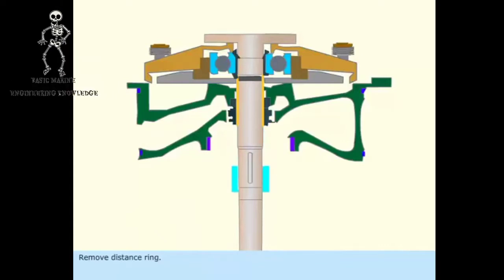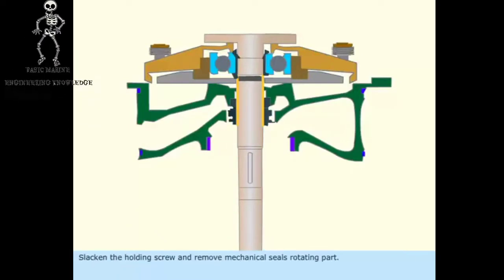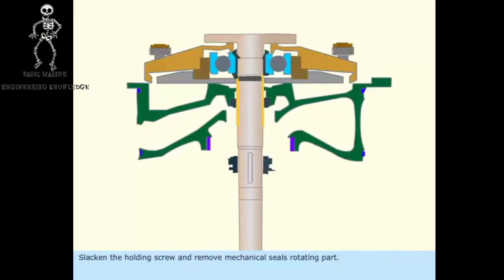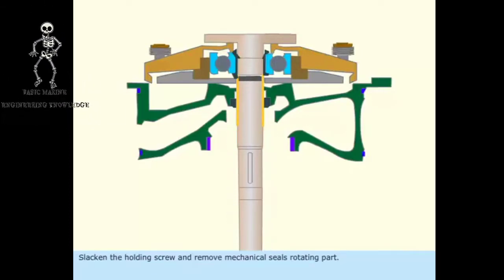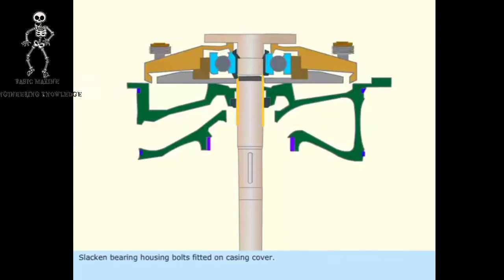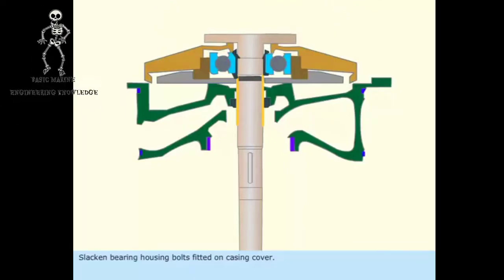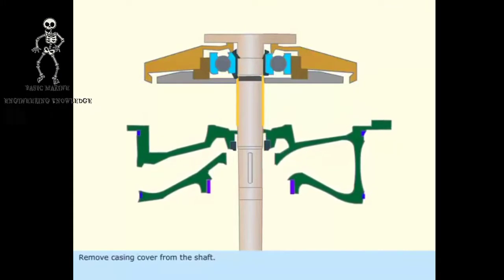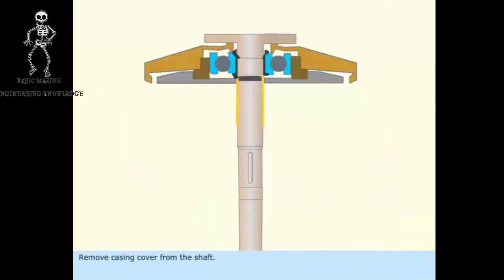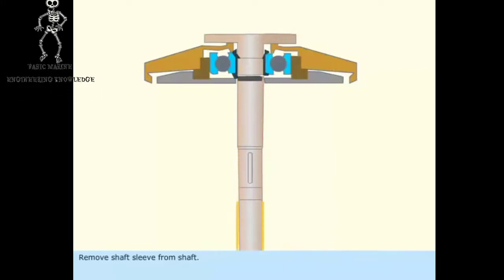Remove distance ring. Slacken the holding screw and remove mechanical seal's rotating part. Slacken bearing housing bolts fitted on casing cover. Remove casing cover from the shaft. Remove shaft sleeve from shaft.